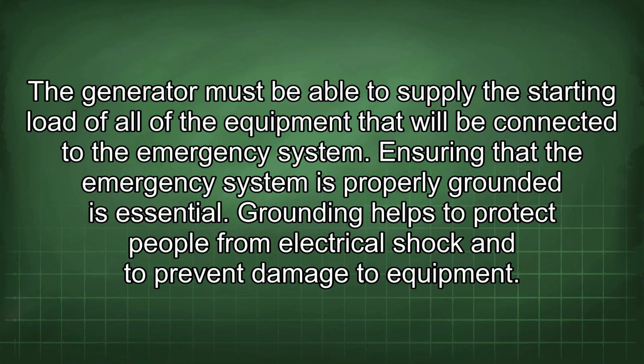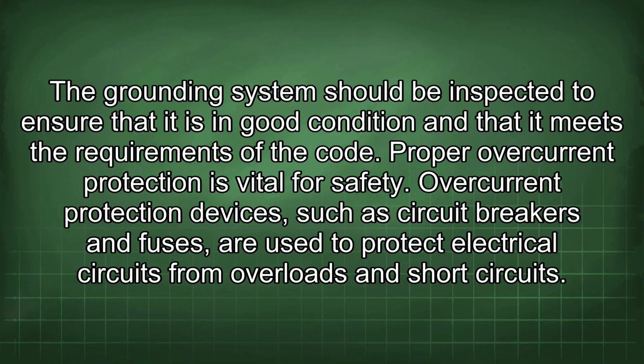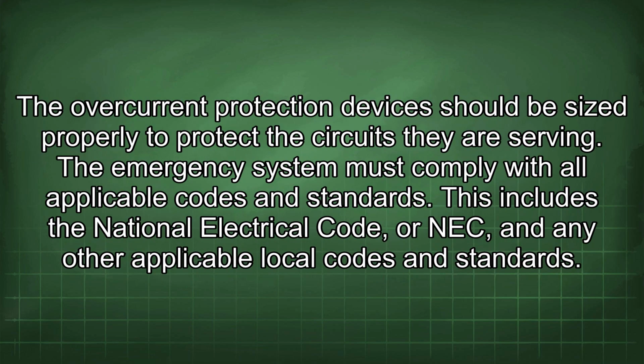the emergency system. Ensuring that the emergency system is properly grounded is essential. Grounding helps to protect people from electrical shock and to prevent damage to equipment. The grounding system should be inspected to ensure that it is in good condition and that it meets the requirements of the code. Proper overcurrent protection is vital for safety. Overcurrent protection devices, such as circuit breakers and fuses, are used to protect electrical circuits from overloads and short circuits. The overcurrent protection devices should be sized properly to protect the circuits they are serving.